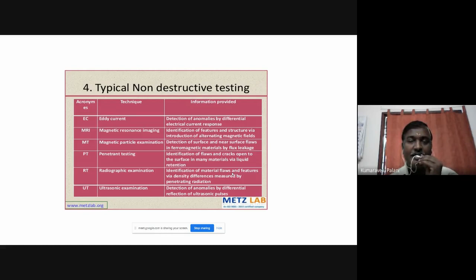For example, if the thickness is 10 mm, we can give a tolerance of minus 15 percent. At least the shell and disc portion should measure 8.5 mm thickness. Then that equipment can be fit for use. Otherwise, if it is less than 8.5 mm, what can we do? No post-mortem work will happen. We destroy the equipment and replace it with new equipment. Because what will happen? There is a possibility of a burst. That's why we give much more importance to non-destructive testing.